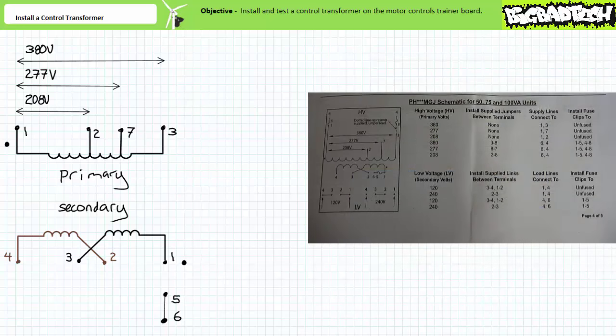Note the wiring diagram shows that in order to set up this control transformer for a 208 to 120 volt conversion, we need to supply primary terminals 1 and 2 with any two phases of our light industrial three-phase AC system. These would be the H1 and H2 primary inputs for a simplified control transformer schematic.